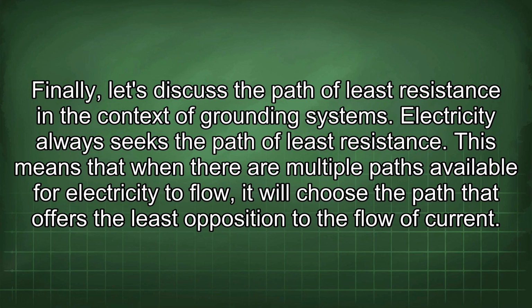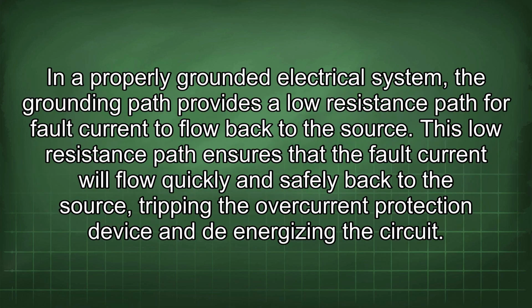Finally, let's discuss the path of least resistance in the context of grounding systems. Electricity always seeks the path of least resistance. This means that when there are multiple paths available for electricity to flow, it will choose the path that offers the least opposition to the flow of current. In a properly grounded electrical system, the grounding path provides a low resistance path for fault current to flow back to the source. This low resistance path ensures that the fault current will flow quickly and safely back to the source, tripping the overcurrent protection device and de-energizing the circuit.